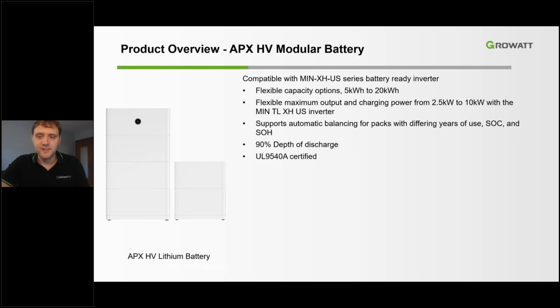So our next battery solution is the Apex High Voltage Modular Battery Pack. This modular battery is set to be released in the next month, so be sure to reach out to your distribution partners to check availability. It features a modular design to stack the battery capacity up to 20 kilowatt hour with a maximum discharge power up to 10 kilowatts. The modular design of this battery makes installation an absolute breeze and allows for greater flexibility for your customer's system. The Apex battery can be installed from floor to ceiling in one single battery cluster to save space on the wall, or can be divided into two separate battery clusters.